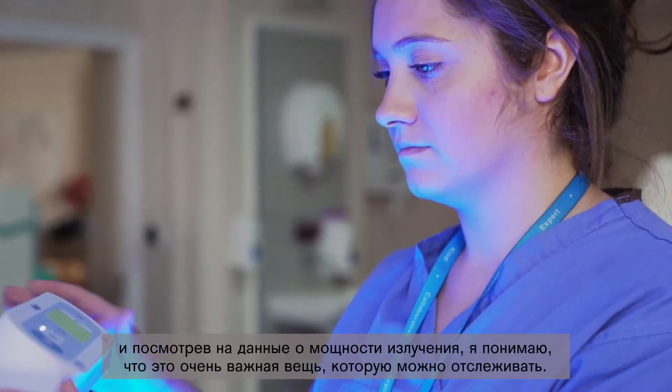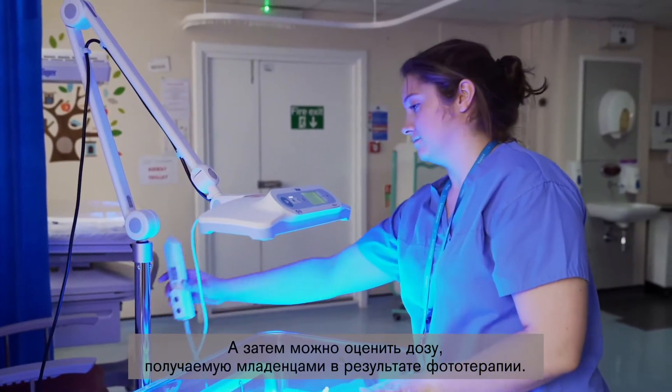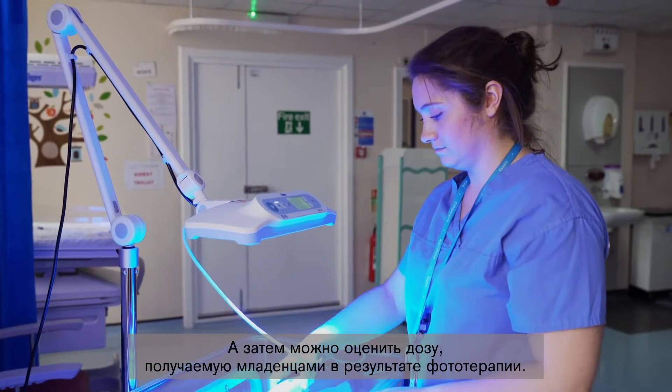Nurses and doctors in the UK have grown up with the concept of single, double, and triple phototherapy. We believe the distance between the baby and the light should be about 30 to 40 centimeters — most units follow 40 centimeters. But the concept of irradiance is very little understood. Having worked with BiliLux for some time and reviewed the data, I feel it's very important to monitor and estimate the dose delivered from phototherapy to babies.